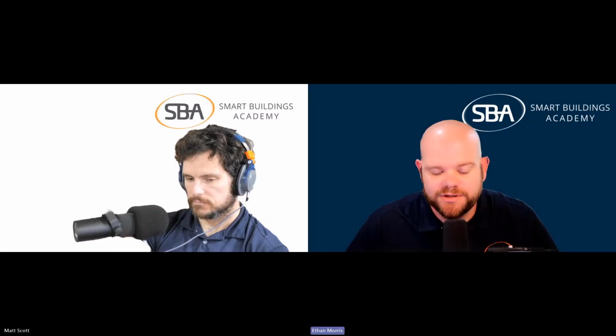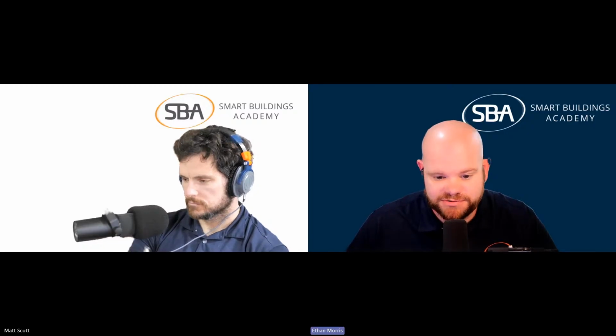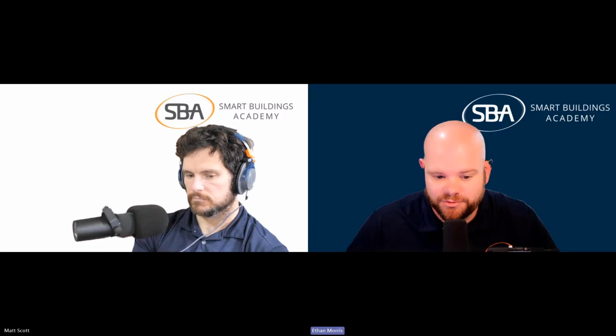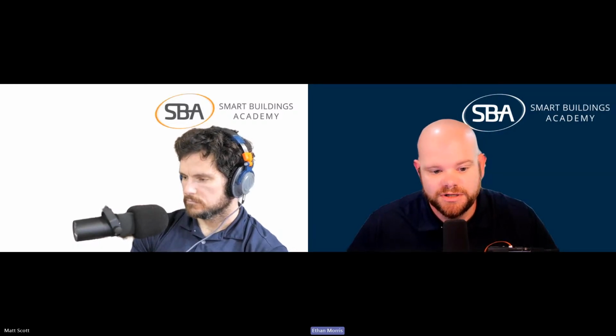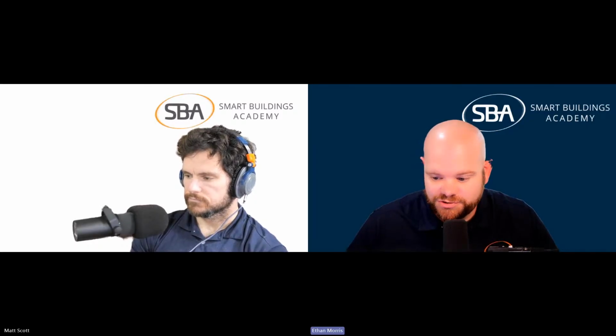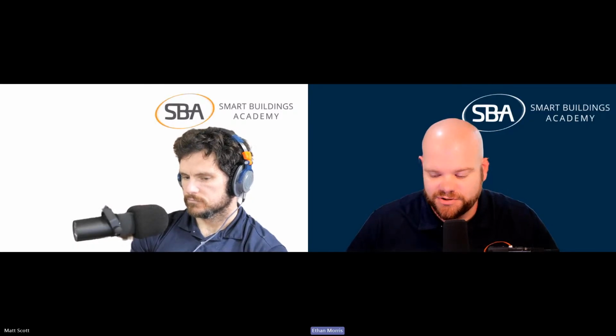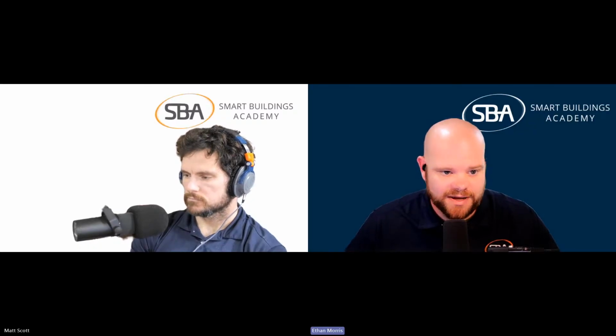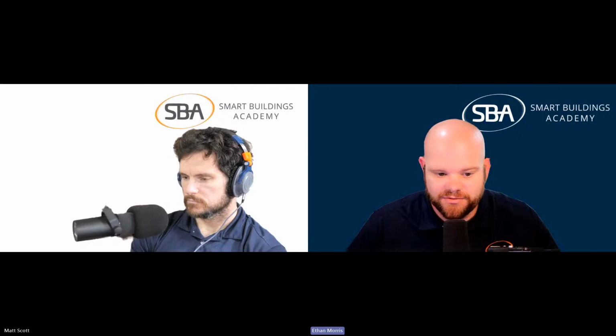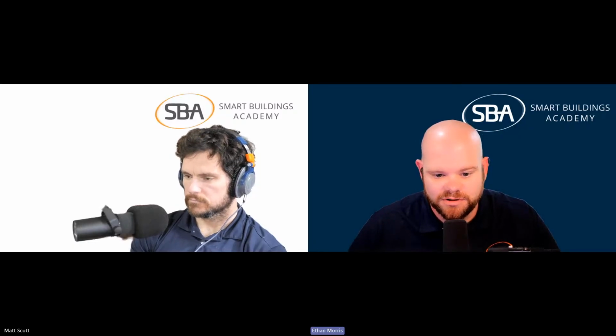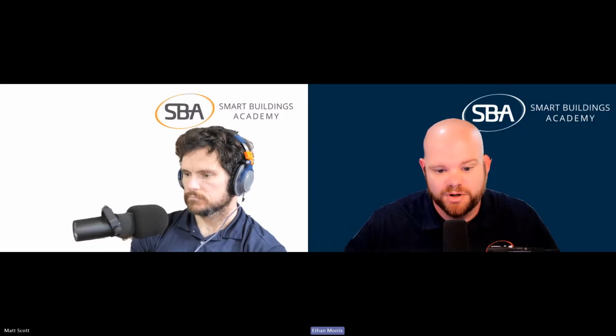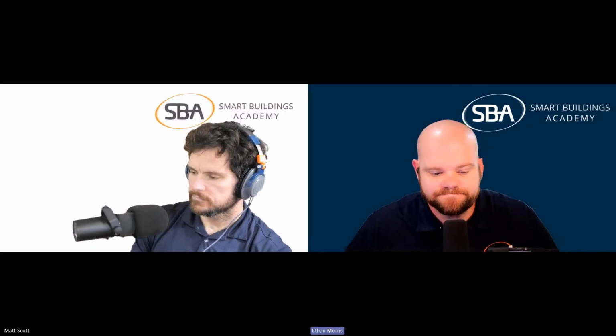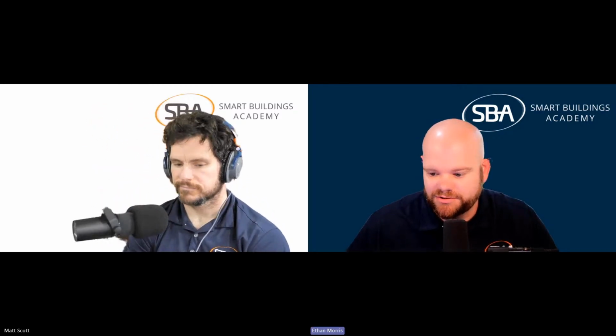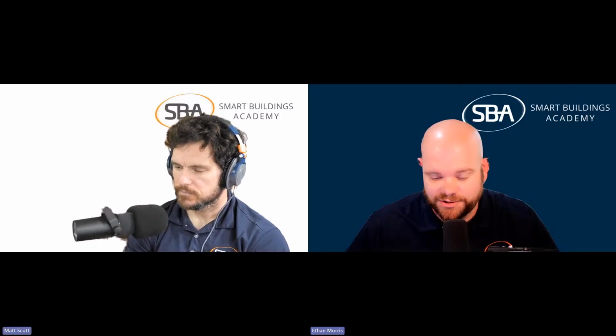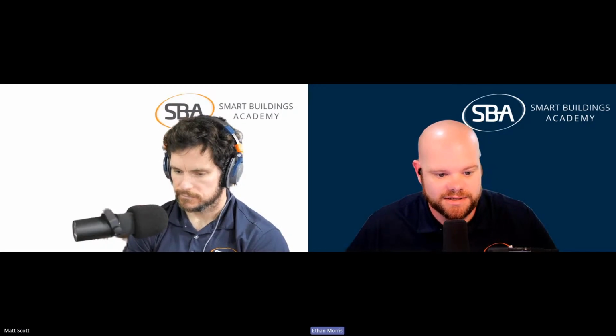Then within the indoor units, you have the EEVs, the electronic expansion valves, and these are different from a thermal expansion valve, which is what traditional systems used. Electronic expansion valves are usually a pulsed valve, with a range of anywhere from 0 to 2,000. Manufacturer baselines change how they operate, but most of what I've seen are pulsed valves, so they open and close, pulsed very slow. The reason they're electronic is because they can modulate the flow of refrigerant going into and out of the fan coil unit. That also helps with your energy efficiency, things of that nature.